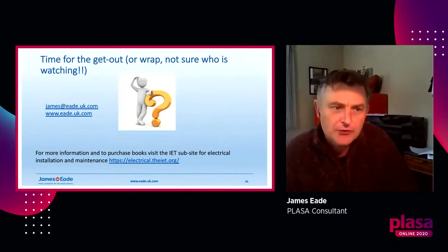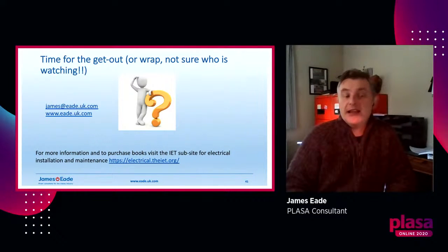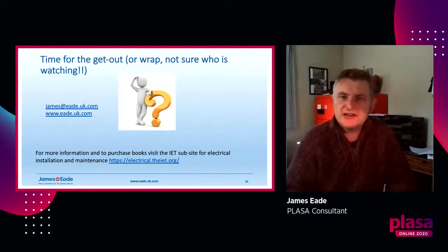Steve, hello. If you're using your own equipment on roadshows regularly and vigilant of equipment condition, what would be sensible testing periods and recording practices? Well, if it's your own kit, legislation still applies because you're at work. So in terms of checks, again, Class 2 appliances, your visual inspection every time you use it might be perfectly good enough. Class 1 equipment, I don't know, because I don't know what kit you've got.